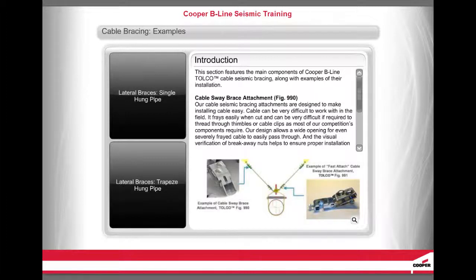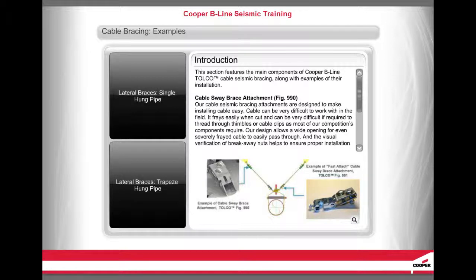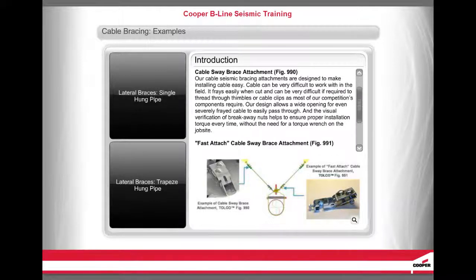This section features the main components of Cooper B-Line Tolco cable seismic bracing. The Cable Sway Brace Attachment, Figure 990, is designed to make installing cable easy. Cable can be very difficult to work with in the field — it frays easily when cut and can be difficult to thread through thimbles or cable clips as most competition's components require. The design allows a wide opening for even severely frayed cable to easily pass through, and break-away nuts help ensure proper installation torque every time without the need for a torque wrench on the job site.